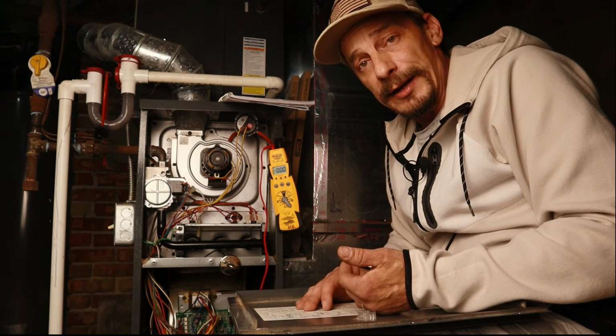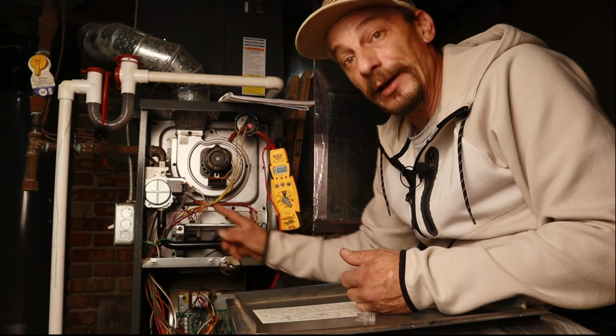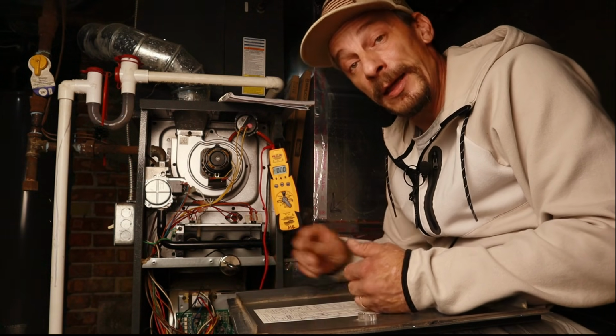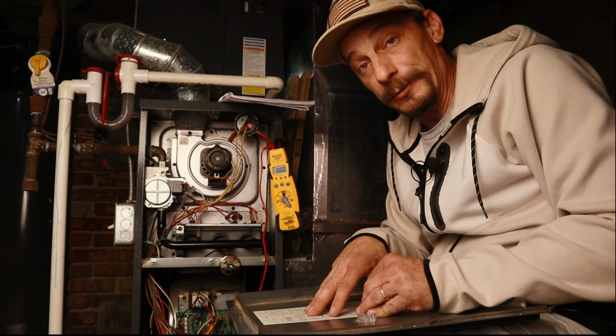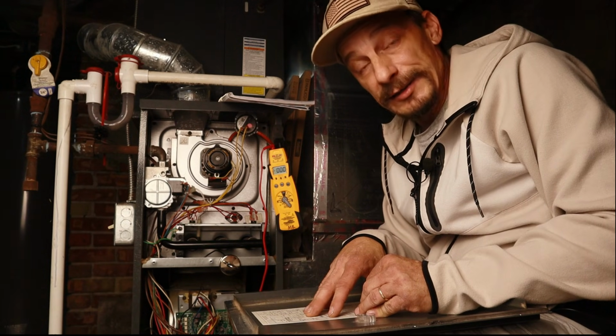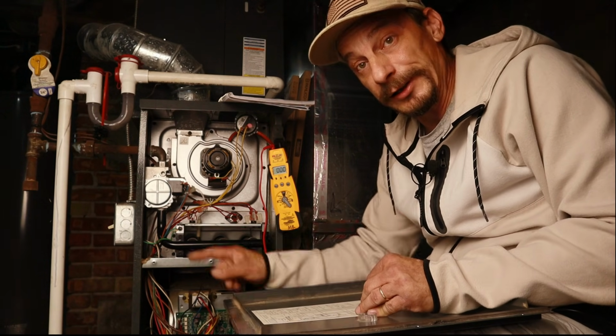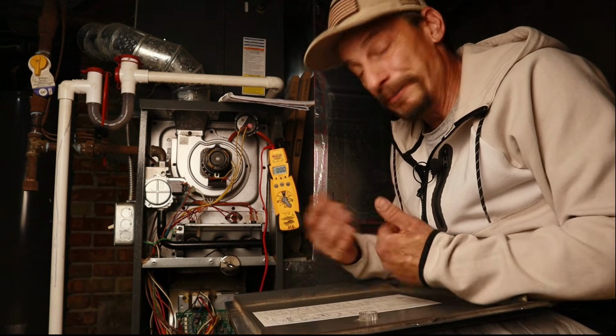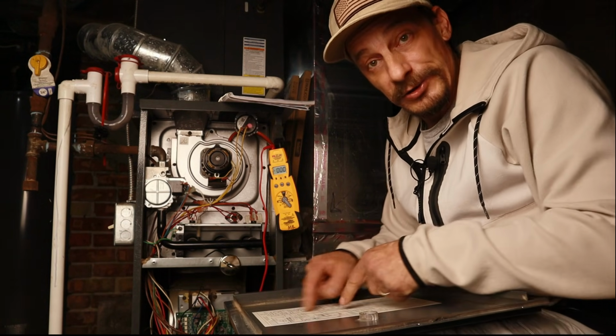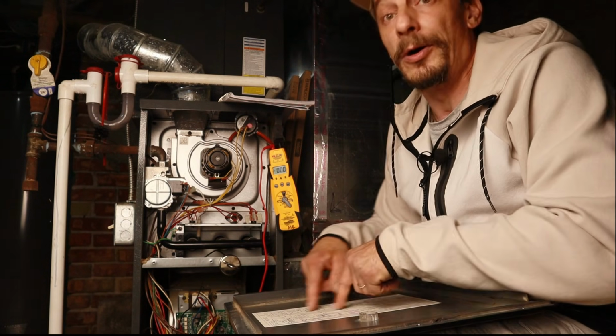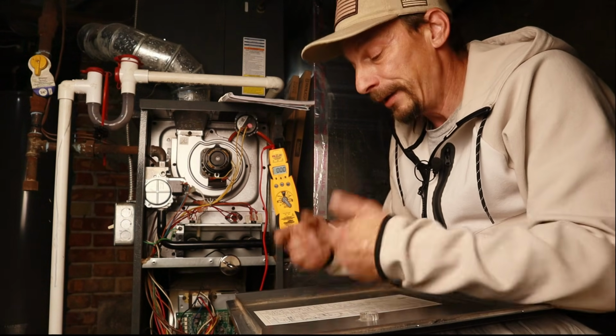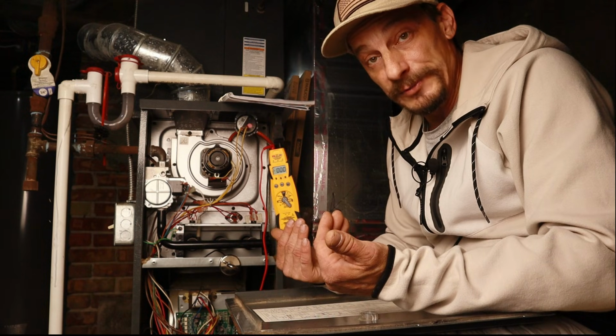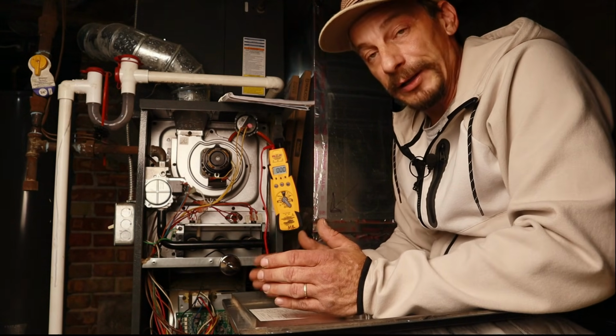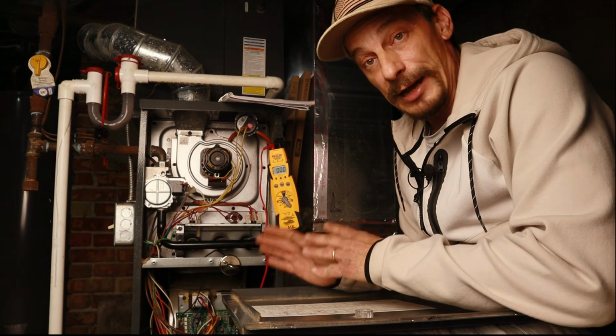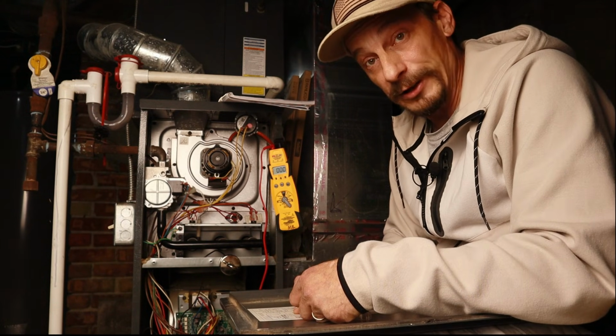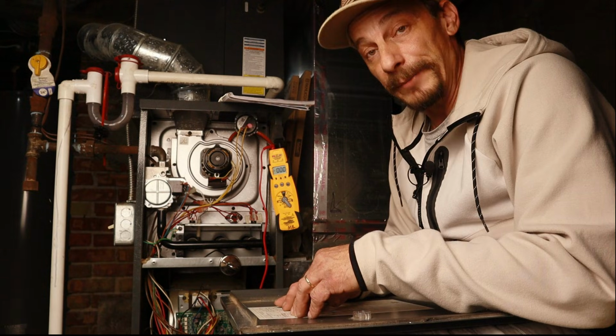So sometimes on schematics, you might see one wired into the other, and you can actually trace it out on the schematic. But if you don't see that, if you see something like the schematic we're working with today, basically the same thing is happening, it's just not one circuit wired in series. It's basically parallel. All these different circuits are getting powered simultaneously, and unless all of them come back to the control board and check out, the control module will shut down the startup sequence. Any safeties at all when it comes to the heating sequence should have 24 volts out to it and 24 volts coming back to this Molex plug so that the control board can be satisfied.